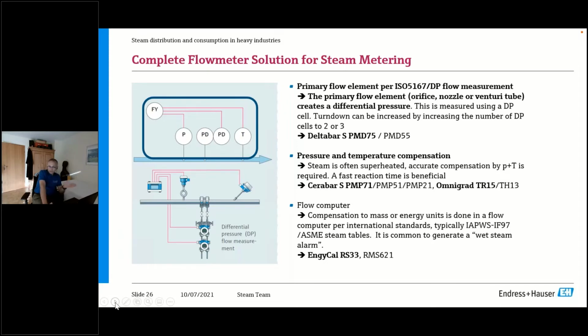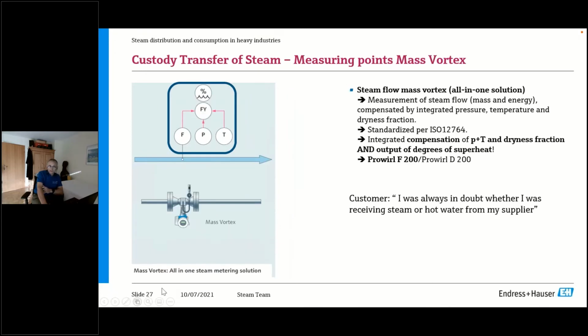For these cases, you can use our Deltabar S PMD 75, and the new generation PMD 55B as well. For pressure and temperature compensation here, I would always use the best pressure and temperature devices. So the Cerabar S, this is the highest accuracy that we can offer, and Omnigrad TR15, a weld-in temperature sensor, typically for these higher temperatures. And you compensate inside your computer, like the EngyCal RS33, that comes with IAPWS data, like the vortex meter that is using the same data.